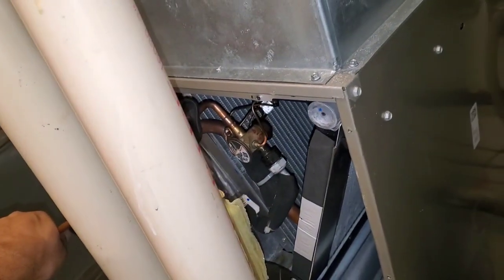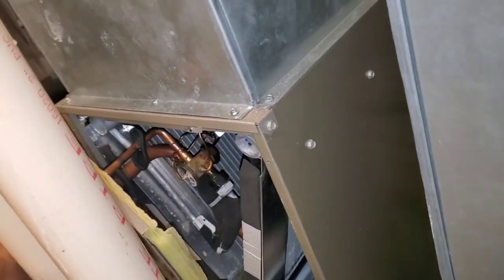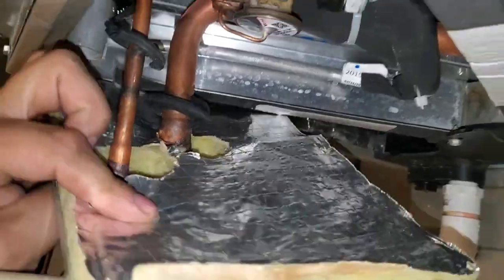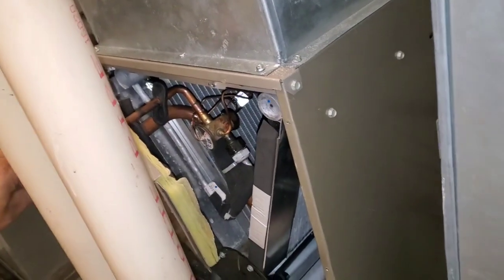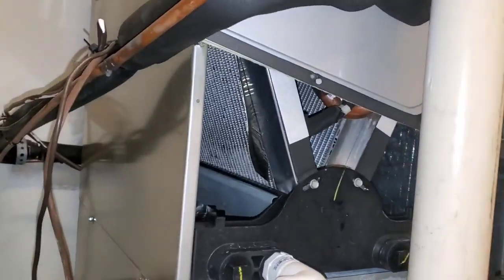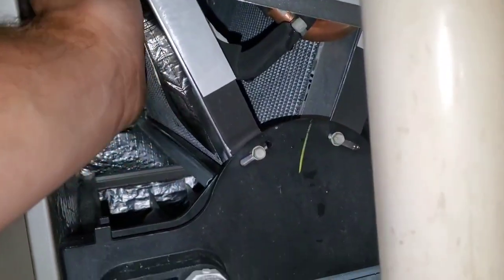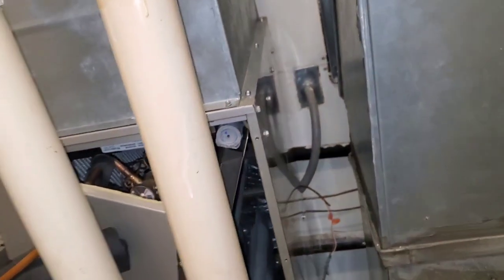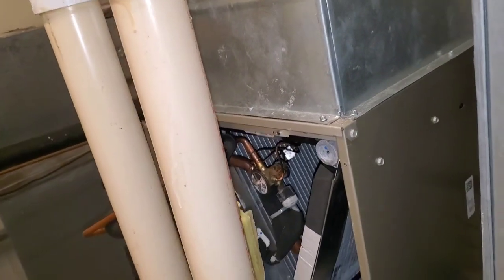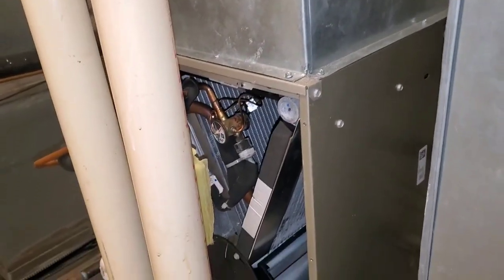And this liquid line felt like a hell of a lot of flash gas before, and now it just feels like a teensy bit of flash gas. I mean, this isn't all waterlogged. Kind of suspicious that maybe our compressor. This is what we got. So I'm gonna put these panels back on, let the system run for a little while, stabilize, and look at the numbers again outside.